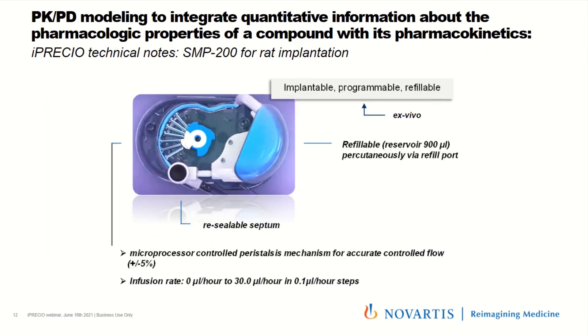At Novartis, we decided two to three years ago to use the iPrecio pumps, which we evaluated in two species — rats and mice. In rats we used the SMP200. Importantly, this pump needs to be pre-programmed before implantation, which limits flexibility somewhat, but it is a very nice tool. Most importantly, it has a resealable septum meaning you can refill the pump more than a thousand times.